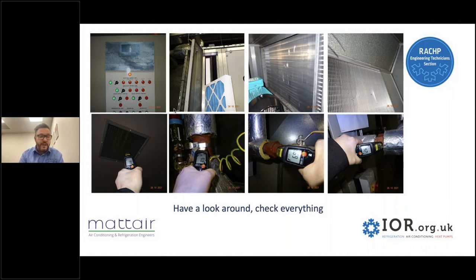Then we move over to the grill, and we can see it's coming out at 19.5 degrees C, no cause for concern. But if you look closer, the next picture along is the chilled water pipe inlet to the air handler, and you can see it's 10 degrees C. It was cold outside, about 9 degrees C, but the chiller was activated, the boiler was activated, and it was 10 degrees C because the chiller valve was passing. Then the next picture shows the frost coil was passing also, and you can see that was 69 degrees C. So that one was passing.